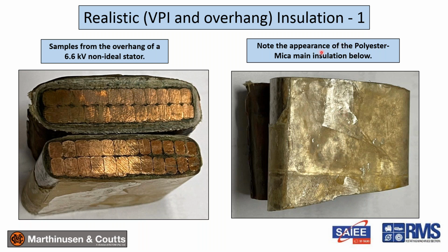Most of the main insulation of modern machines, even machines up to 30, 40 years ago, is mainly mica, backed by either a polyester backing or a glass fabric backing. This is the film backing.